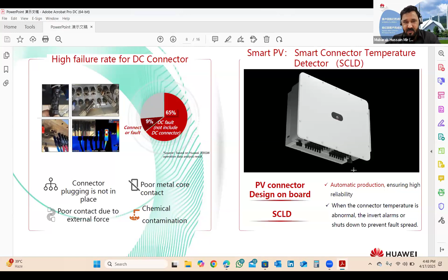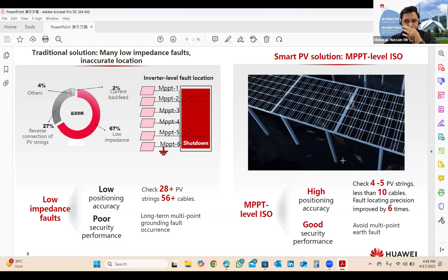Another MPPT level disconnect function is available. Normally, in larger scale power plants, when we are going for 10 megawatt, 15, 20, 400 megawatt or 1 gigawatt level power plants, the O&M cost is a very important factor. If any fault occurs in any location, the inverters are now so smart that you can easily identify which MPPT has a problem. And at every MPPT there are more or less 2 to 3 strings, maybe 1 or 2 strings. You can go there and check those strings and easily solve those problems, rather than shutting down the whole plant and incurring a lot of cost for the O&M sector. So this is another feature that is already available in the inverter.